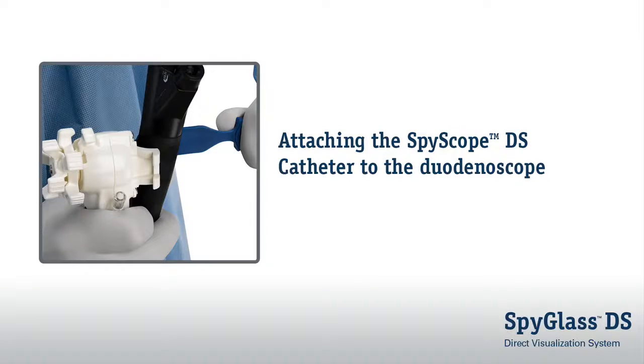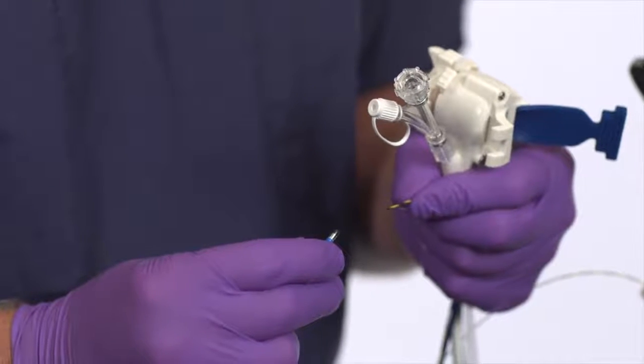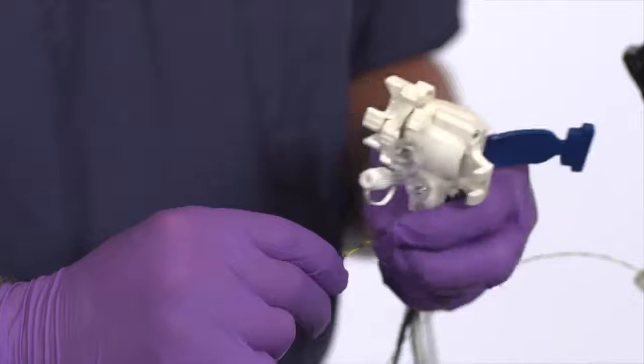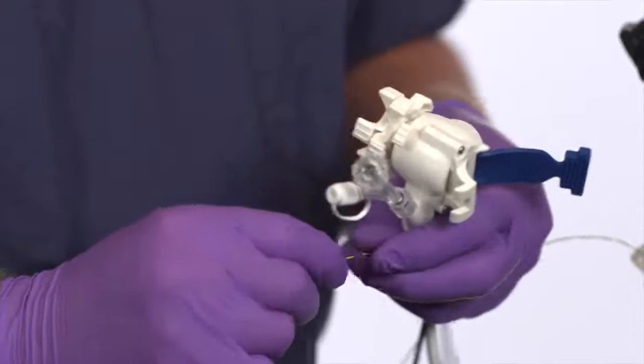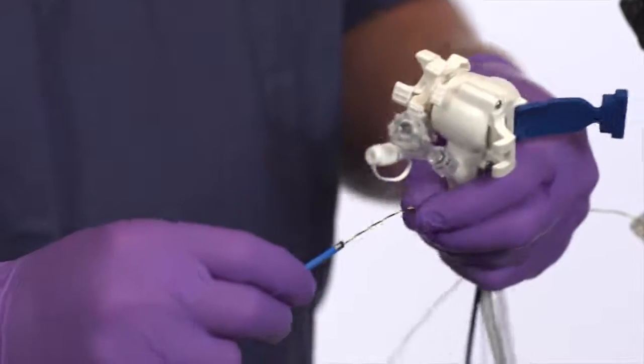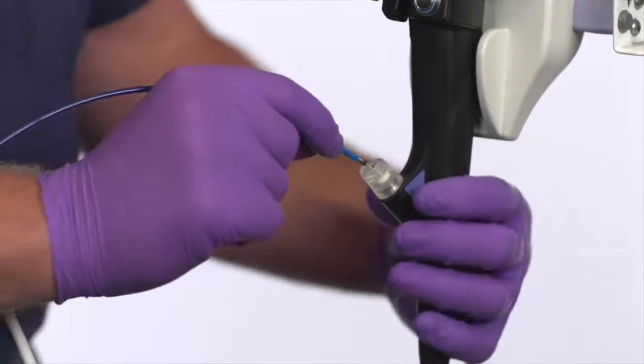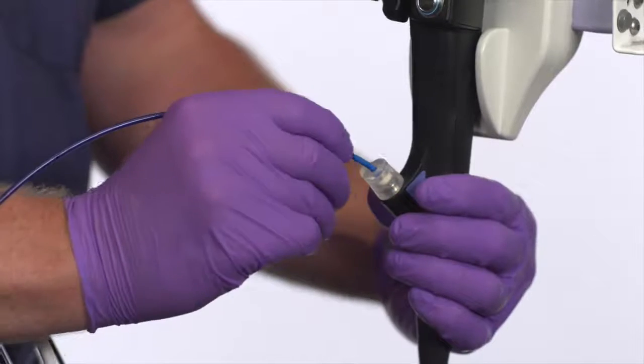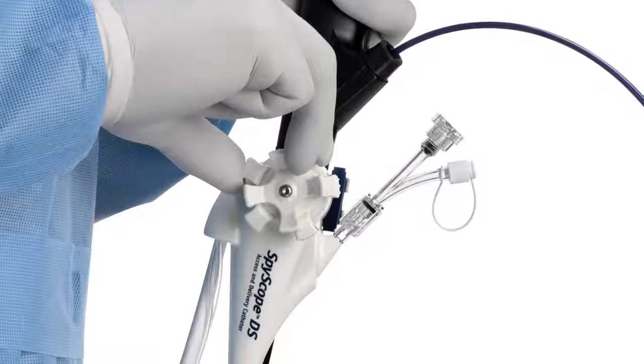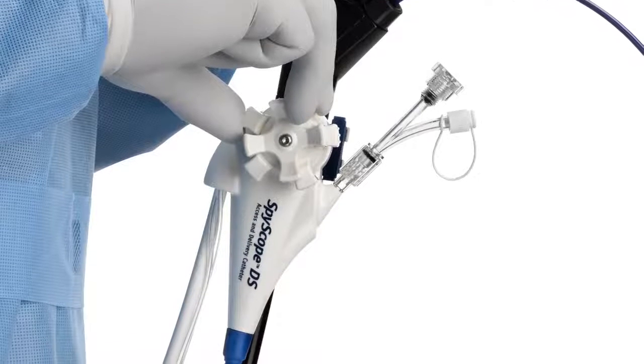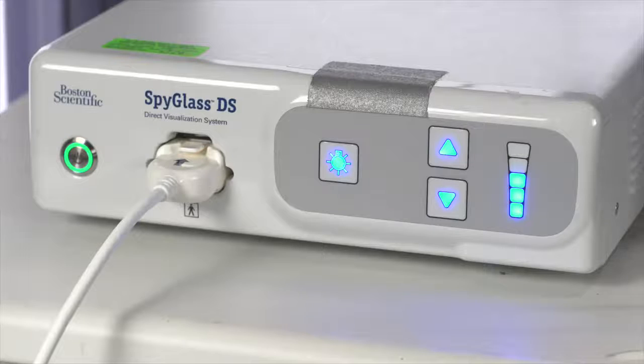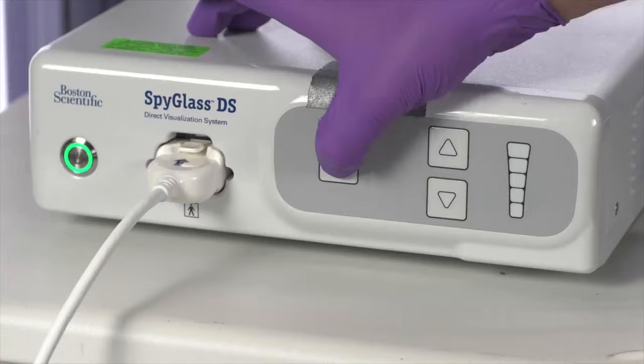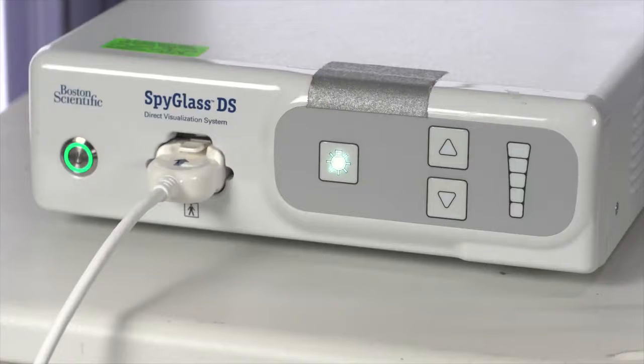Attaching the SpyScope DS catheter to the duodenoscope. When using a guide wire approach, backload the previously cannulated guide wire into the duodenoscope working channel and remove other accessories, tome, cannula, etc. Backload the guide wire into the distal tip of the SpyScope DS catheter working channel. If using Y-port adapter, ensure it is in the open position and turn off the light source on controller if necessary to better see the working channel at the distal end of the SpyScope DS catheter.